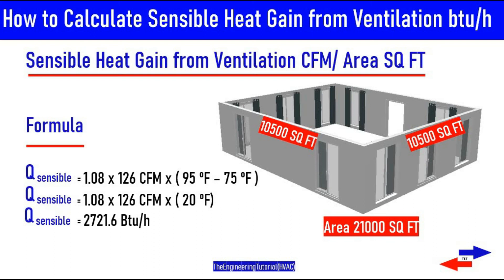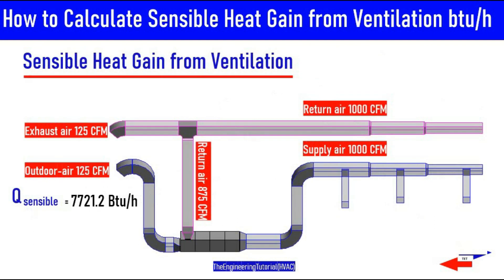For the second example using the CFM per square foot method, we had 126 CFM of airflow. Q sensible equals 1.08 times 126 CFM times (95°F minus 75°F), which gives us 2,721.6 BTUs per hour. Again, remember that this is a coil sensible heat gain, not a sensible space load. That's it for today — thank you for watching.